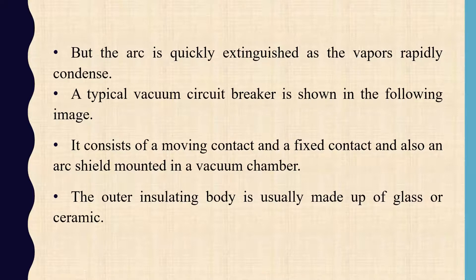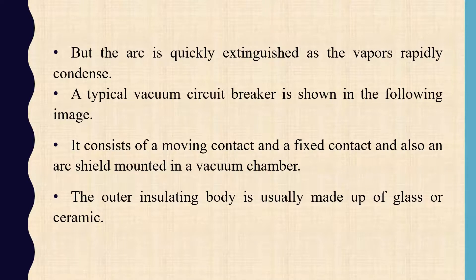The vacuum circuit breaker consists of a moving contact and a fixed contact, and also an arc shield, all mounted inside a vacuum chamber. Inside the cylindrical vacuum chamber, we have the moving contact and fixed contact. The outer insulating body is usually made of glass or ceramic, and the chamber is fully sealed.